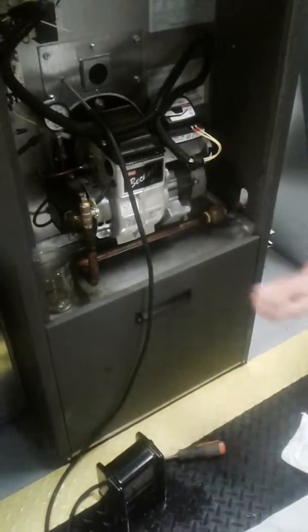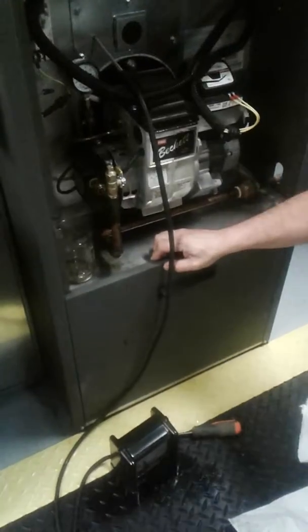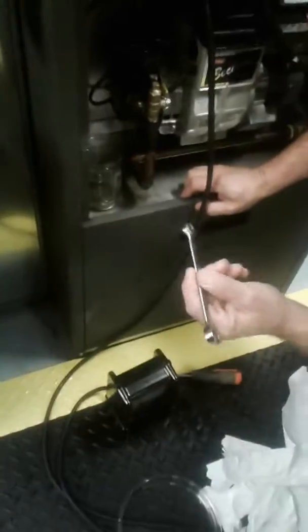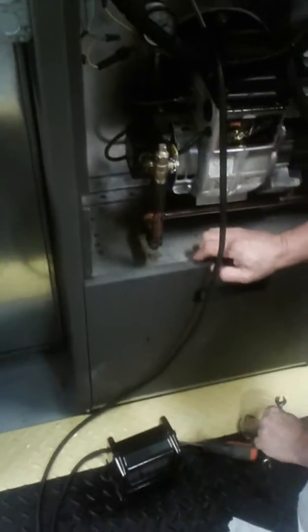Okay, bleed off the air from the oil line and pump. Place a cup under the bleed fitting to catch the oil. All right, so check it out, guys. This is what we're gonna do. We're gonna take the wrench, okay, and open up the bleed valve. This is the bleed valve right here, okay? I have it loose. I want it finger tight because I want to control it, okay?